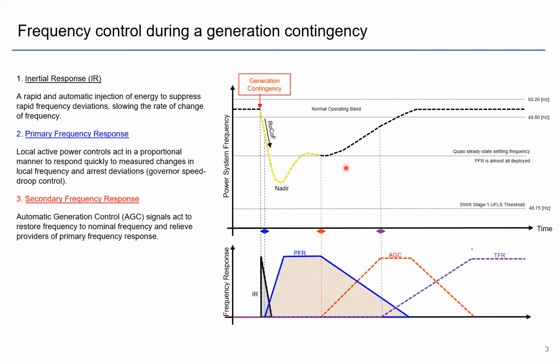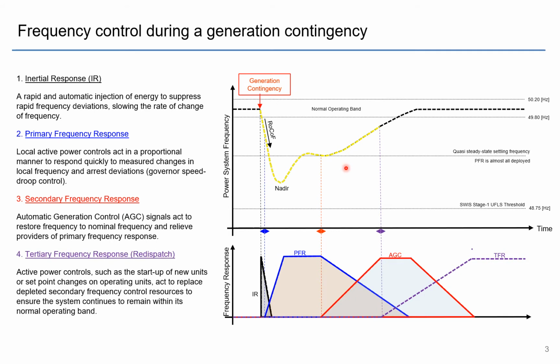What you need to bring it back up is a secondary frequency response, and typically this is done by the automatic generation control system, the AGC, which sends signals to generators to restore frequency back to nominal frequency, basically by upping everyone's active power outputs. So here we see the AGC, or this secondary frequency response, take effect.